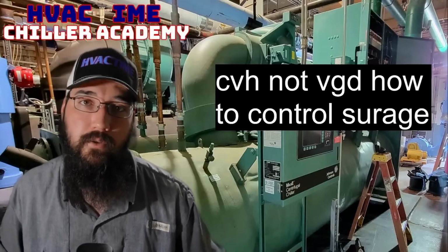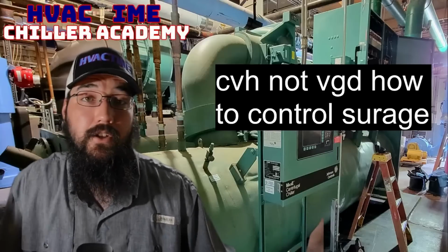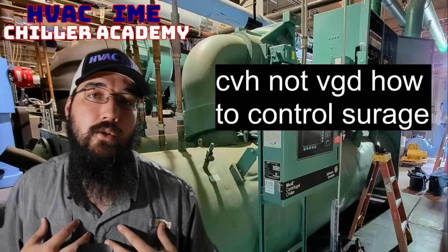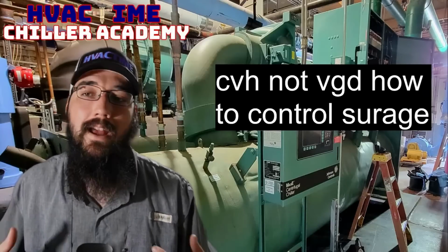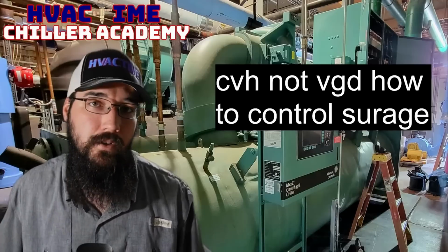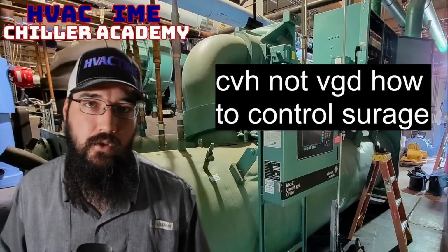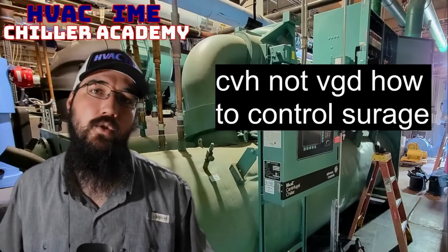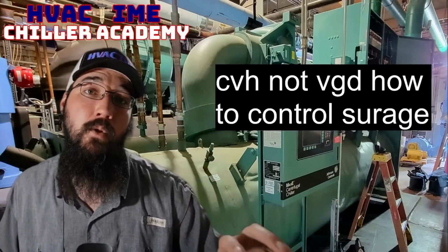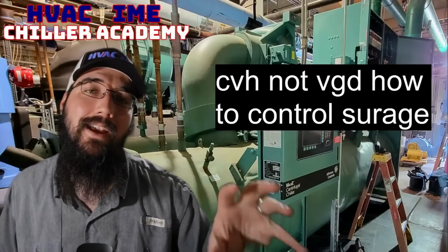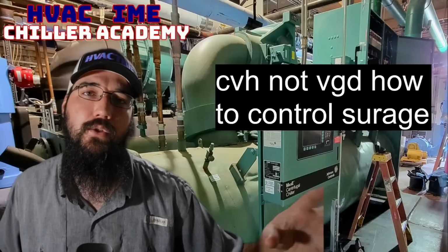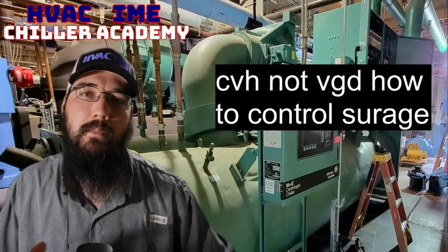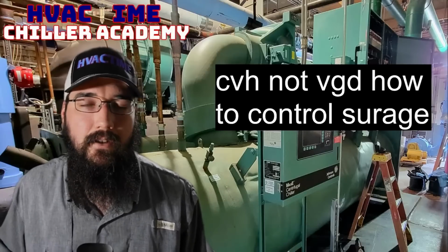I wanted a 44-degree set point. At that stage, it's what the customer had. I can't control the fact that they don't have redundancy. I can't control the fact they don't have parts on hand. I can't control whatever the circumstances are. What I can control is getting this machine at a point where it's not going to kill itself, and then moving on to trying to make the rest of the adjustments that I need from there.